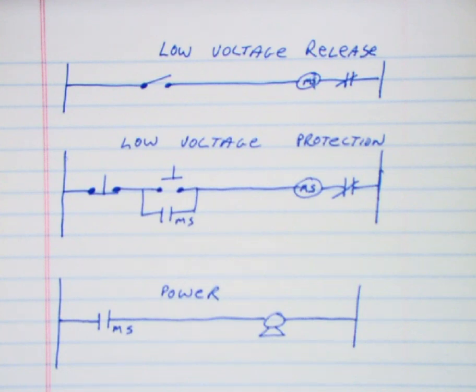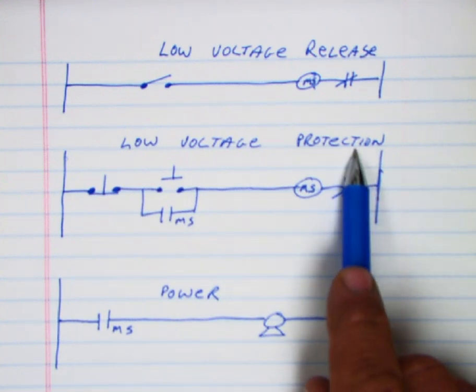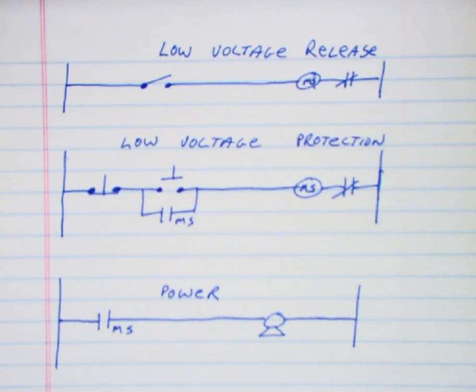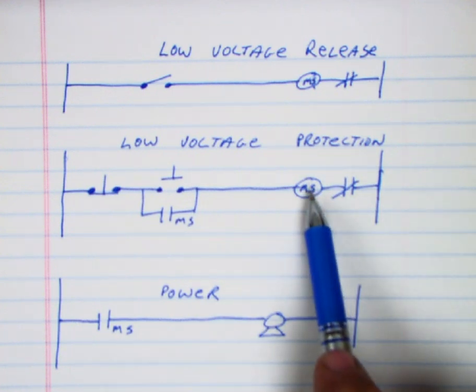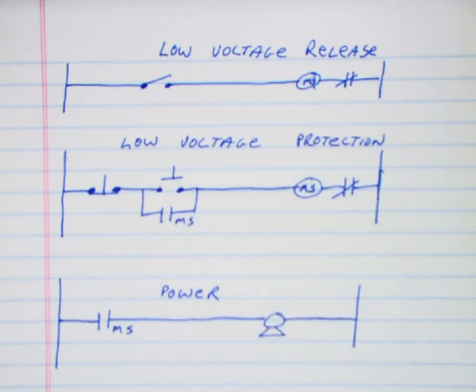The reason we do this, and the reason it's called low voltage protection, is it protects people from this motor accidentally turning back on by itself in the event of losing power or something bumping the switch, the stop switch.